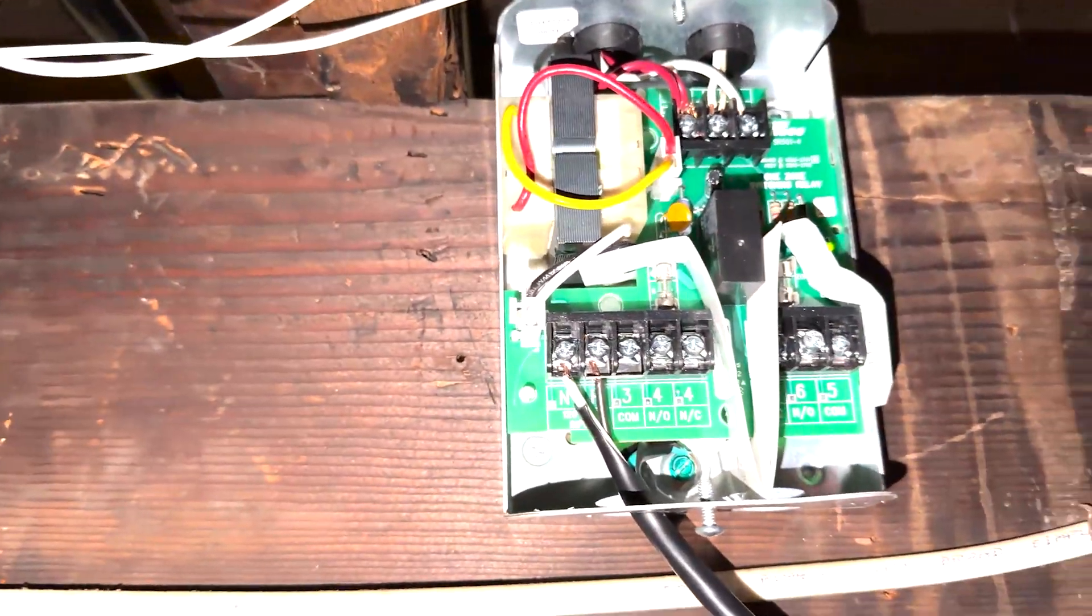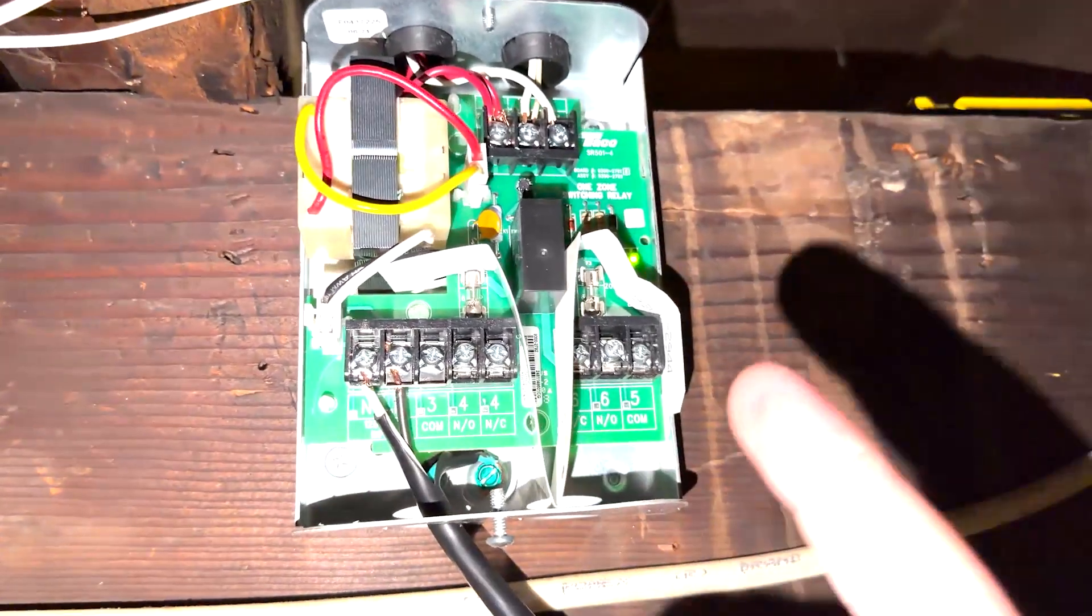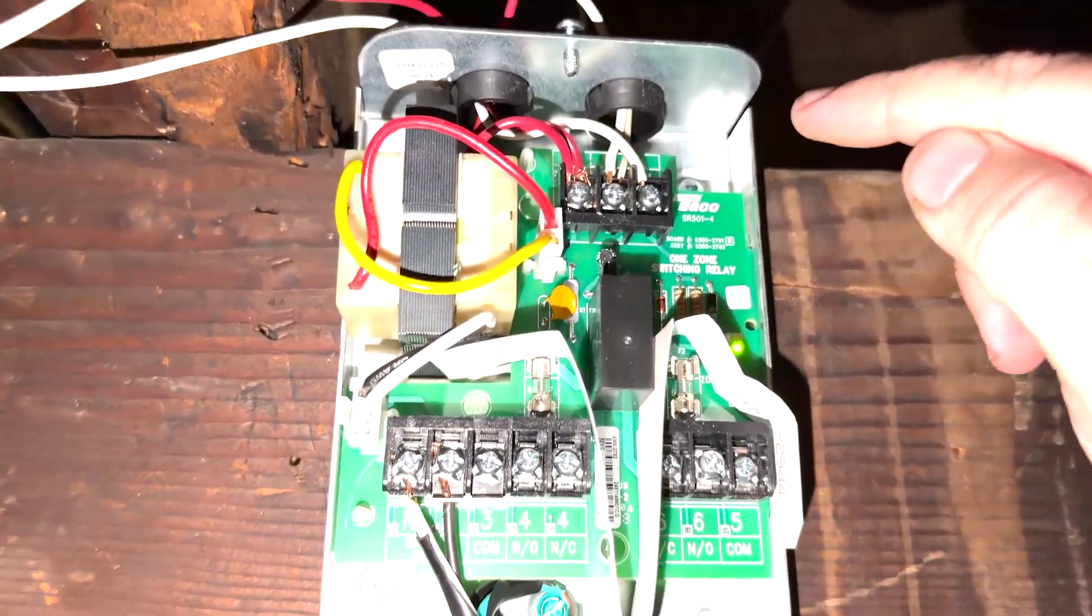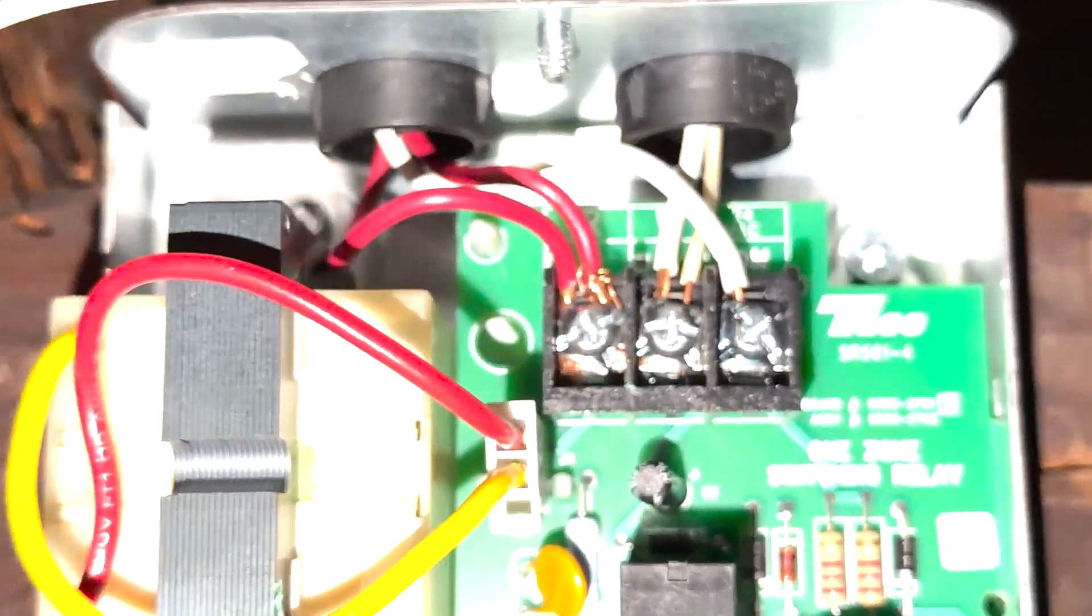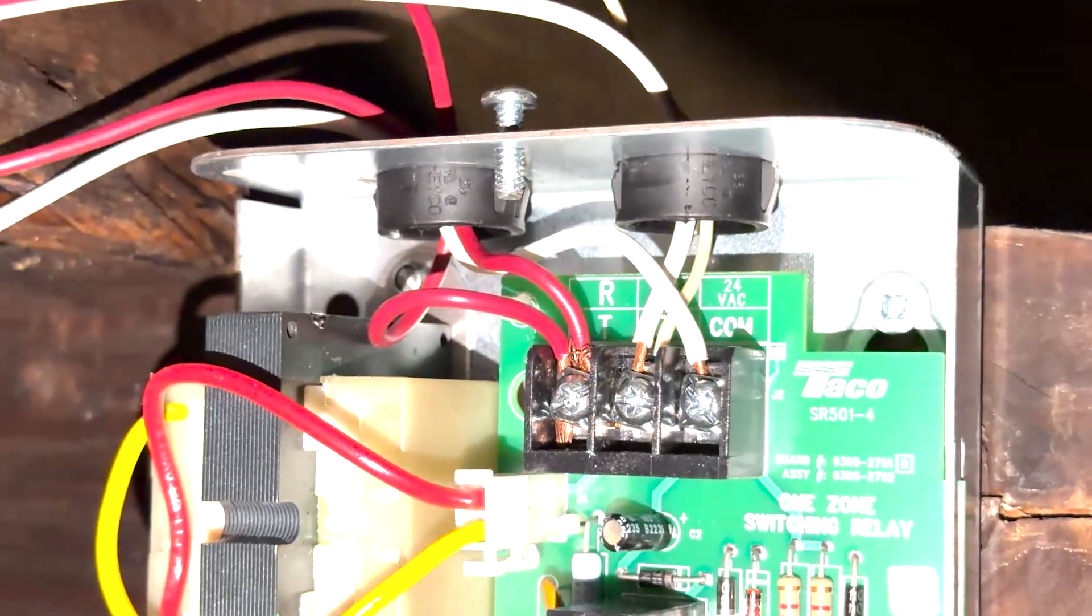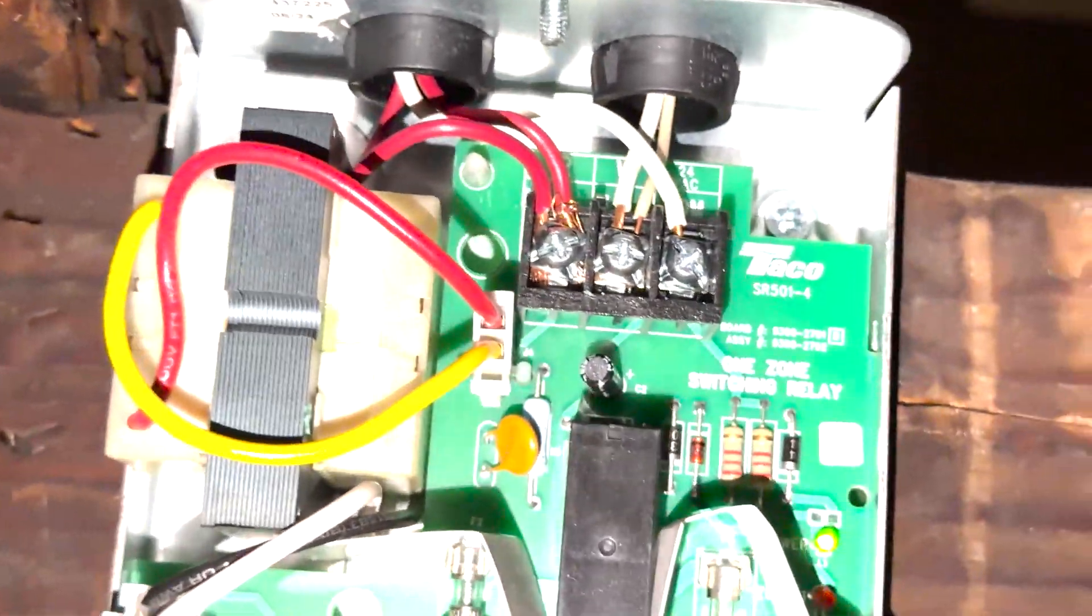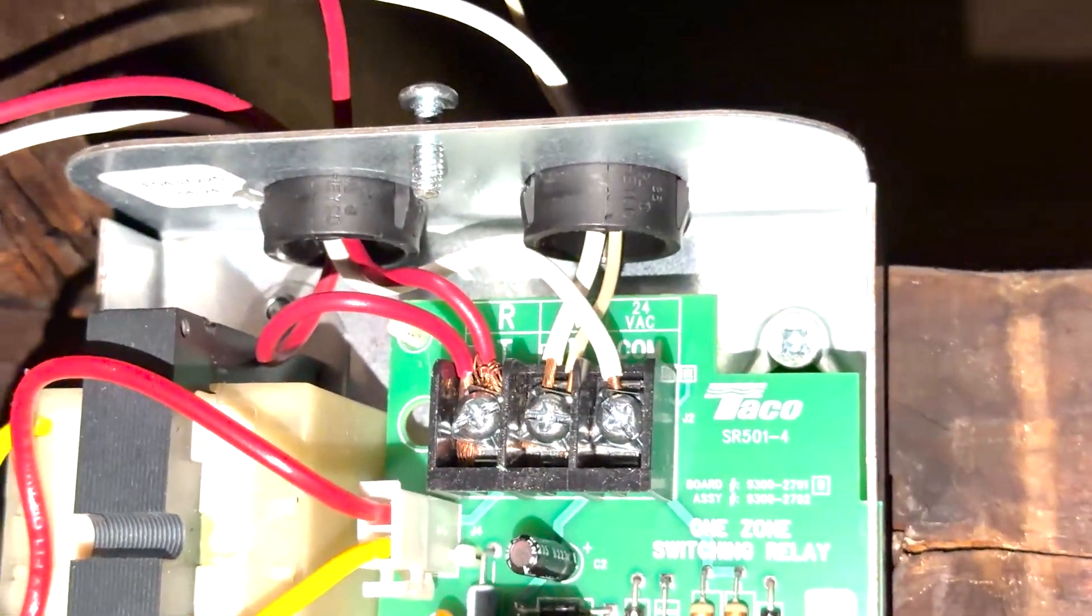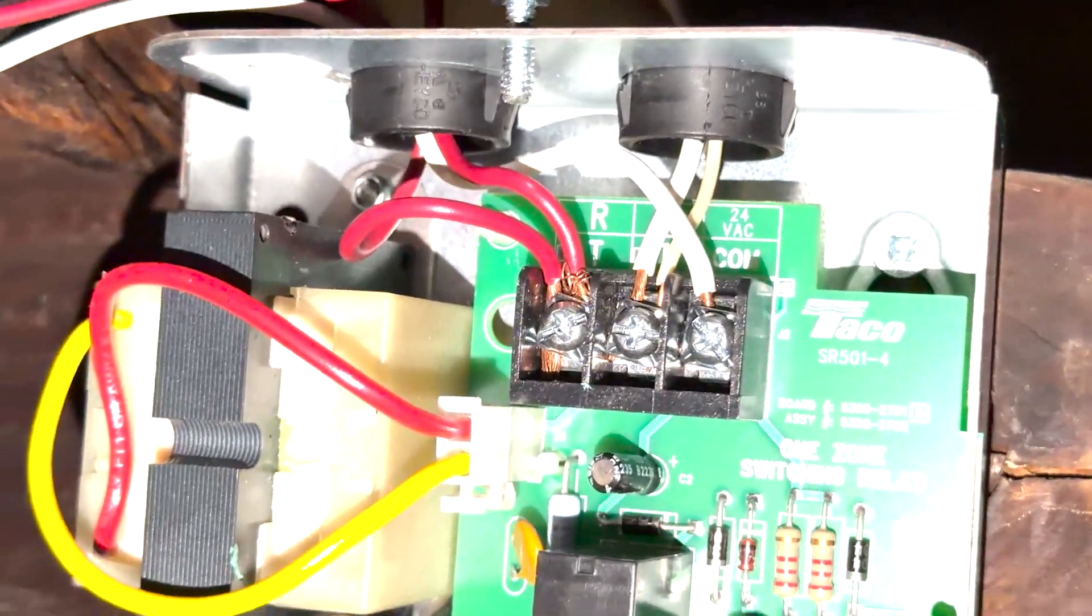So basically what you have to do is you have to take that zone relay and connect the 24-volt transformer to these terminals here. And as you'll see, they're labeled R, T, and 24-volt common as well on the end.